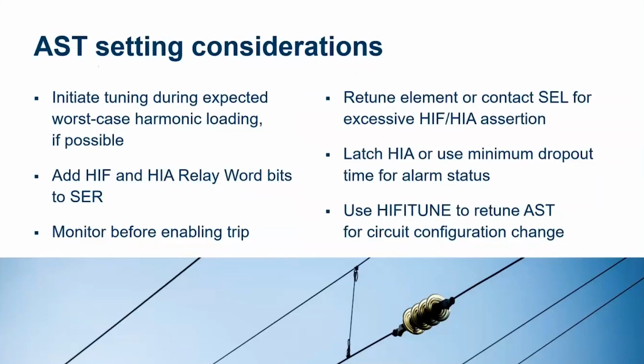For those alarms, they may intermittently assert, so you want to make sure that if possible, especially once things get set up, you're going to potentially either latch those in or tie them to an SV with a minimum dropout time, just to make sure that you're seeing those events. And as mentioned before, the HIFITUNE is something that can be used as part of either manually or automatically initiating a retuning of the system.